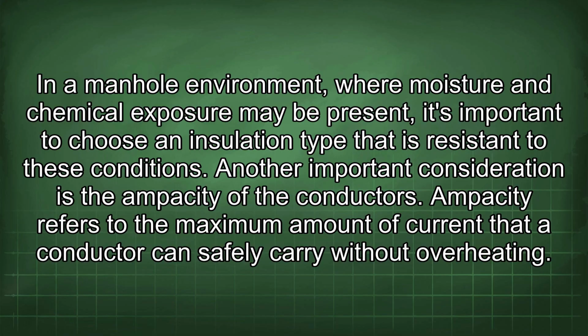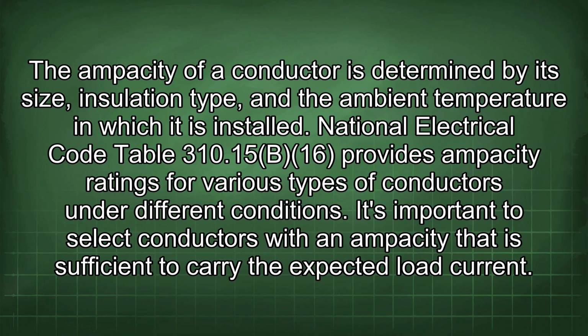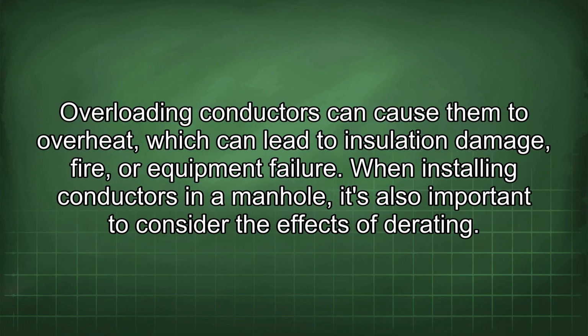Another important consideration is the ampacity of the conductors. Ampacity refers to the maximum amount of current that a conductor can safely carry without overheating. The ampacity of a conductor is determined by its size, insulation type, and the ambient temperature in which it is installed. National Electrical Code Table 310.15(B)(16) provides ampacity ratings for various types of conductors under different conditions. It's important to select conductors with an ampacity that is sufficient to carry the expected load current. Overloading conductors can cause them to overheat, which can lead to insulation damage, fire, or equipment failure.